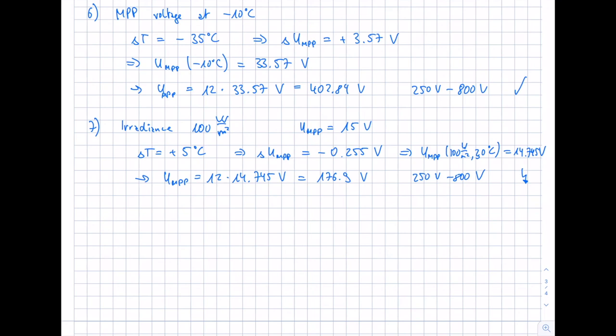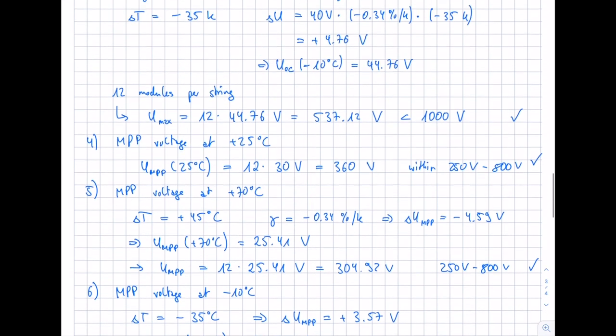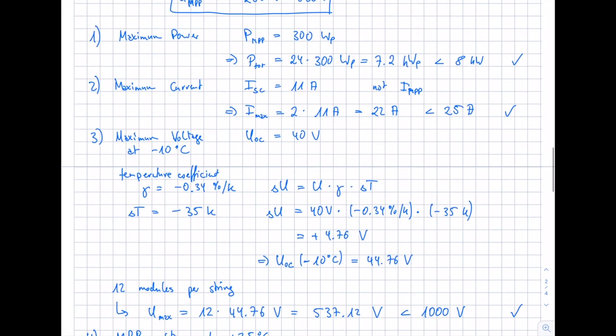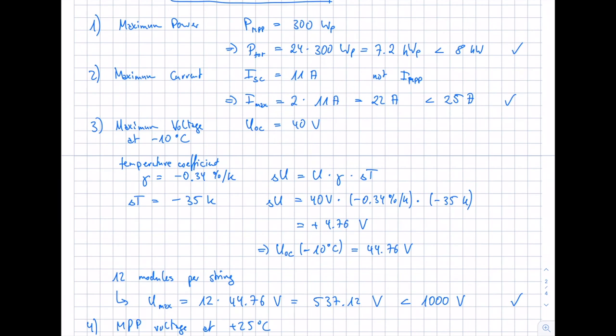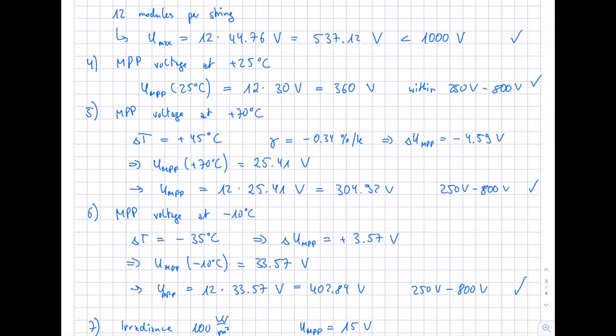Criterion seven not being met is not a critical problem as long as criteria one through six are all fulfilled. The most important criteria are one, two, and three — maximum power, maximum current, and maximum voltage — because failing these could damage your inverter. Criteria four through six ensure the inverter operates within the MPP range under normal conditions, giving you maximum yield from your PV system.